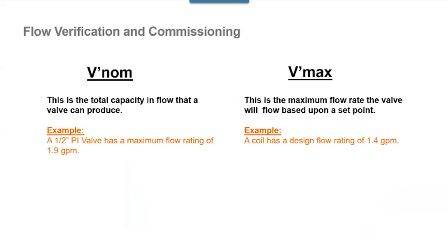On that previous slide, I had a comment about Vnom and Vmax, and I want to discuss this just briefly. These are Belimo terms, but every manufacturer has some translation of these terms. Vnom is the total capacity and flow that a valve can produce. On that example I had, 1.9 is the maximum flow I can get out of it. Vmax is the setting based on the coil. If I have a coil that's 1.4 GPM, I want to set that valve so fully open, it's 1.4 GPM. You're going to hear me come back to Vnom and Vmax in a little bit, but again, it's the nominal flow of the valve and the maximum set value of the flow.